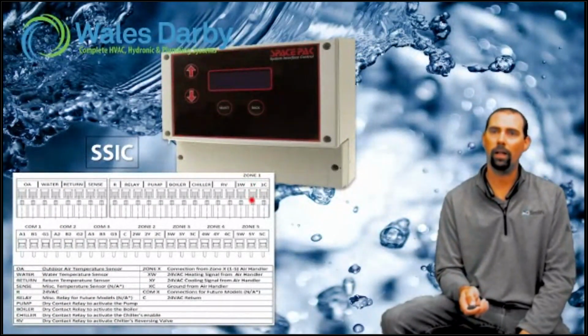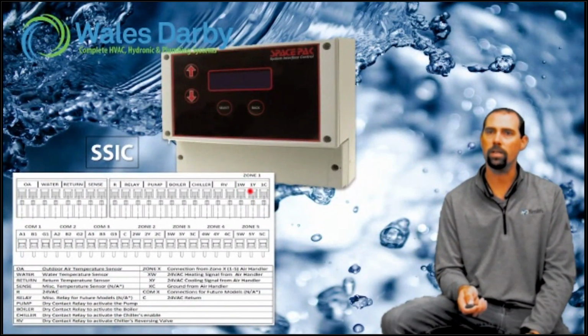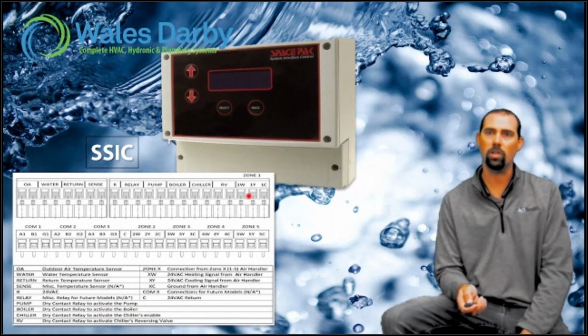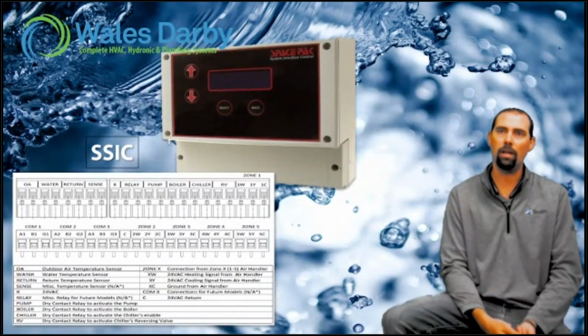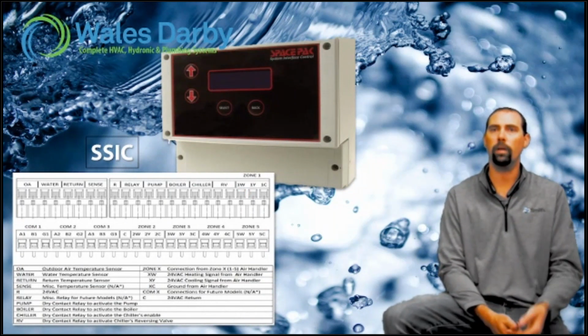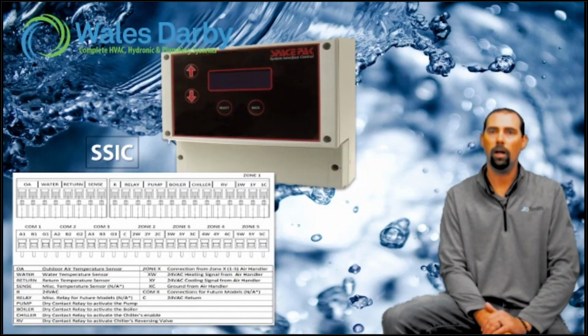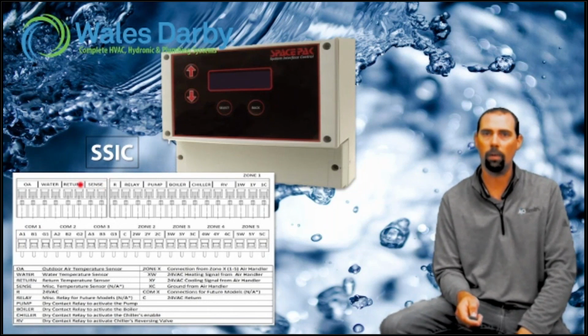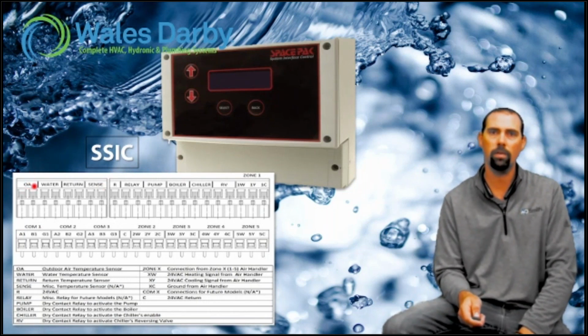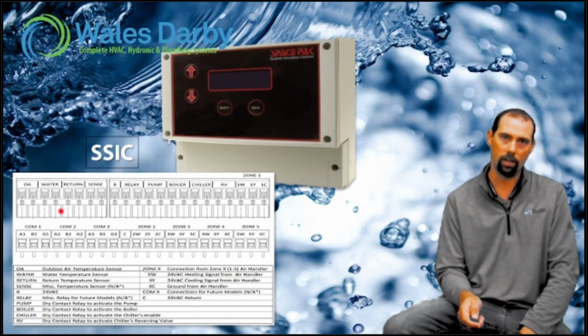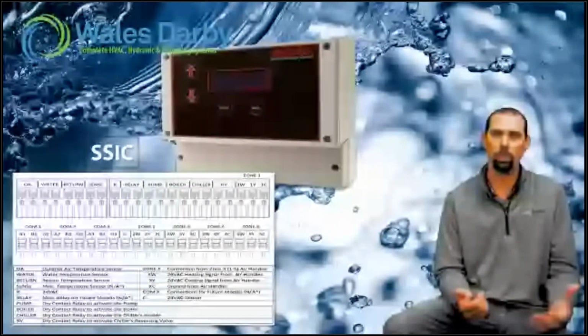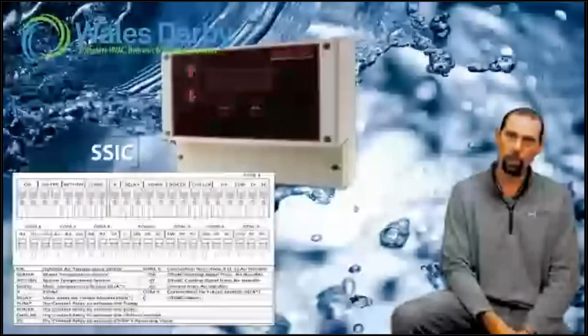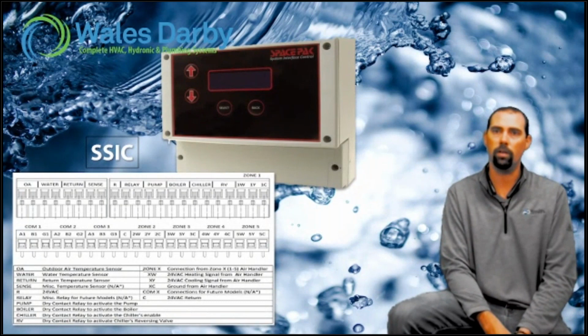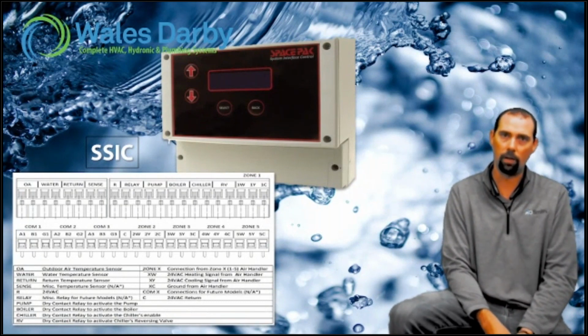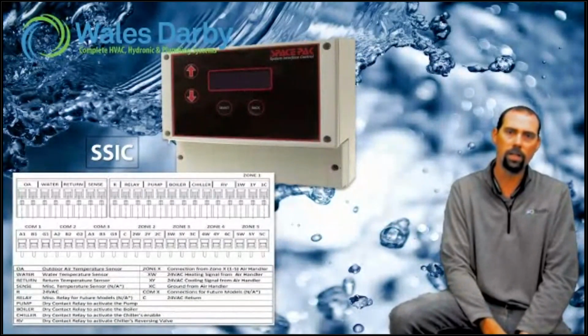So whether our air handler or our baseboard or whatever it is that's calling, we're gonna send an input back to this unit so that it knows and can tell the heat pump, all right, we're in heating, we're in cooling, we need to maintain this temperature in the tank. You'll see that the sensors are all gonna get hooked up to the top left here. We got an outdoor air sensor, we got our buffer tank sensor, we can sense our return temps. So all of this will help with the heat pump operation. We can set some outdoor temps there too if we want to do different shutdowns and drop some temperatures just like we do with outdoor reset. So very easy to operate.